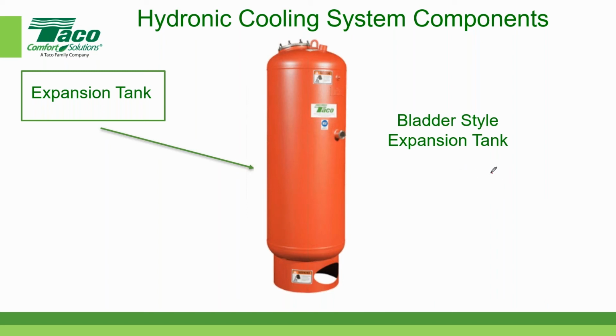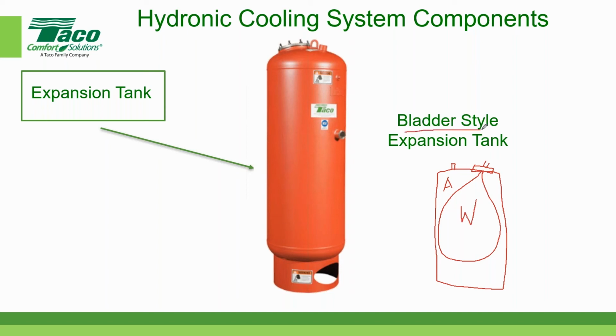So if we have an expansion tank, here's the metal container, similar to the one on the left, and then there is a connection at the top of this tank where you can connect a pipe, and on the inside of that connection is the bladder. The bladder is where the water goes. Then over here in the steel container is a Schrader valve. That's the same valve that you find in your tire. So this is the air side of the tank. Put an A in there. The bladder is connected to the water side of the tank, and that's where it gets its name, bladder-style expansion tank.